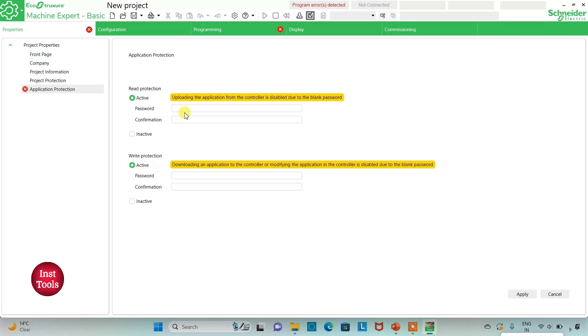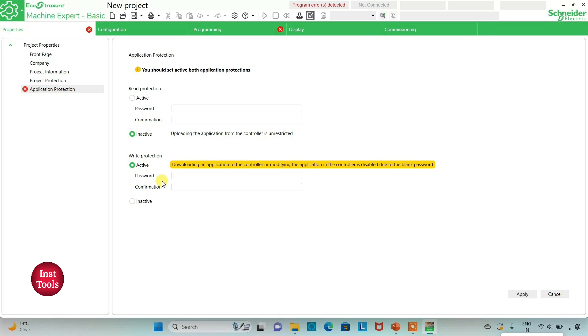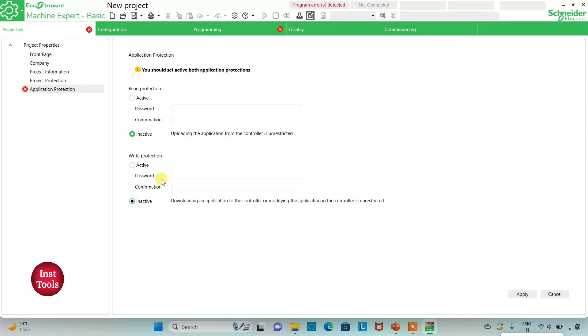then uploading the application from the controller is disabled due to the blank password. That means if we keep it active, we have to set a password here, and then uploading will be restricted — it will need a password. Downloading or modifying the application in the controller will also be restricted and will ask for the password. So for now I will keep it inactive for both read and write protection, and then I will click on Apply.